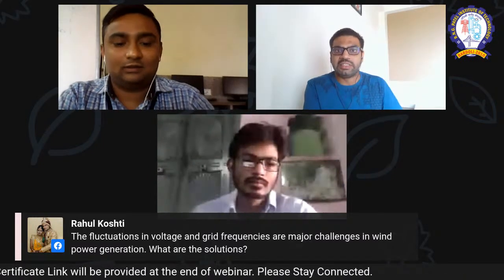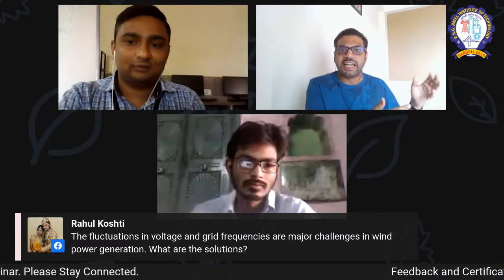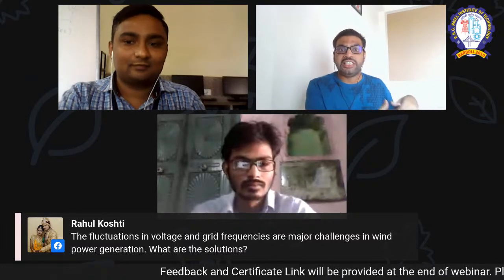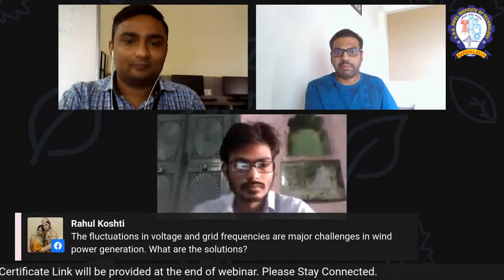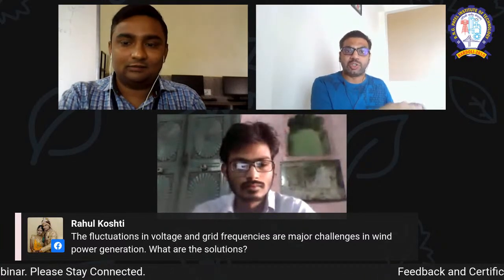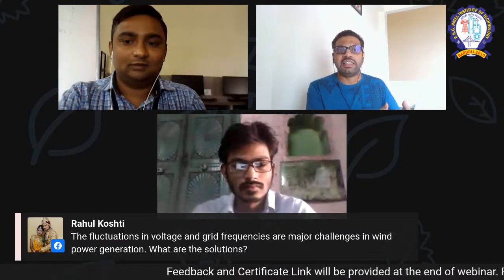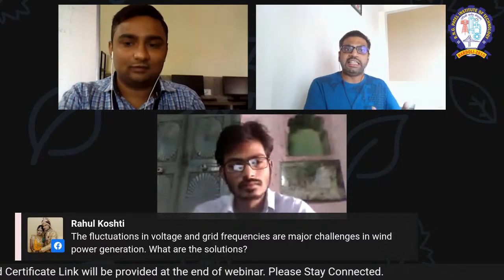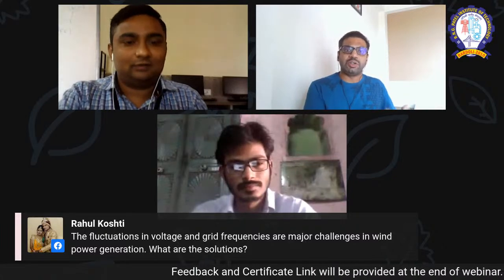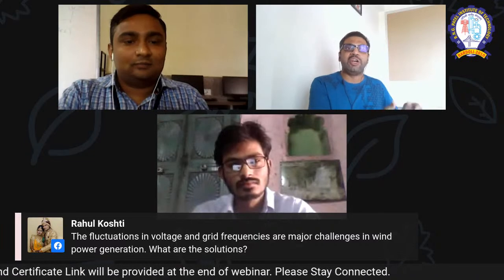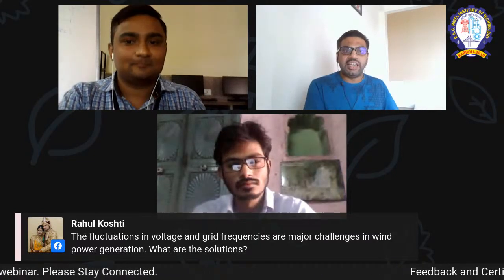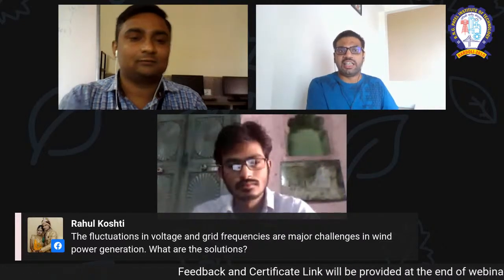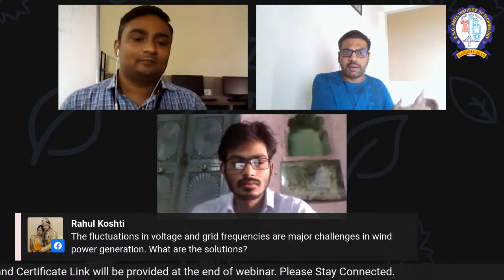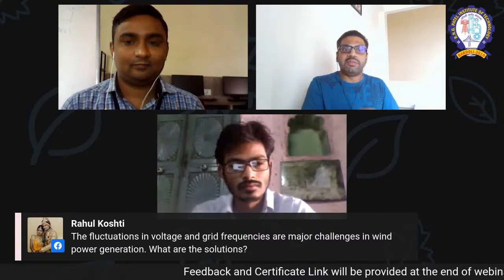In case of grid frequency disturbance, there is a connect-disconnect arrangement, so the wind turbine is disconnected temporarily. It might be a change in frequency due to a change in wind speed or another fault of the generator or converter assembly. For such disturbance, the solution is to go with any FACTS devices. In India we have the FACTS controller, but it is still inside the laboratory. Or you can go with LVRT capability machines. However, there are certain solutions and challenges with the conventional power system. Likewise, thermal and hydropower plants are also implemented with grid-tied wind energy systems at large scale, but that result has not been achievable. So we keep the conventional technique aside and use a power electronic converter mechanism to address these issues, particularly voltage and frequency.